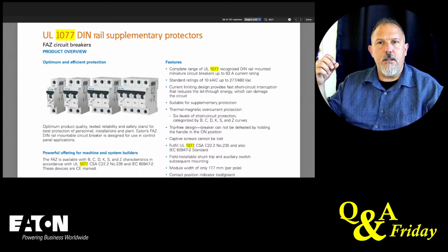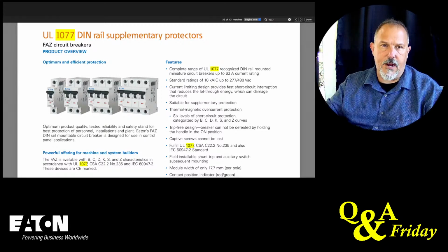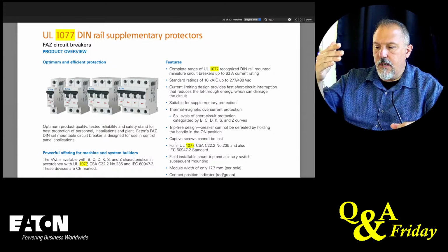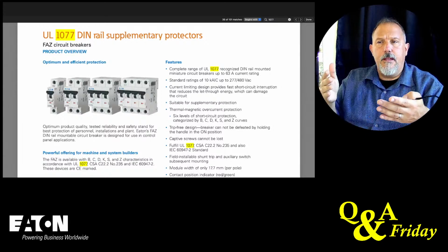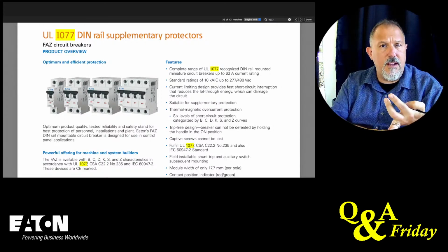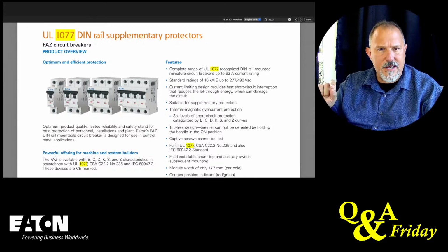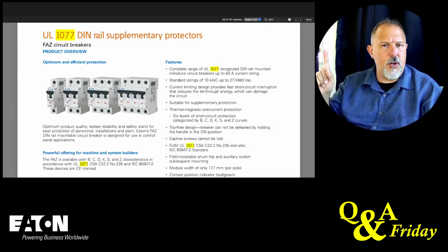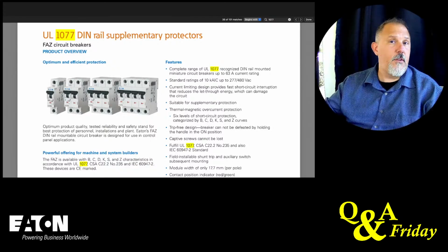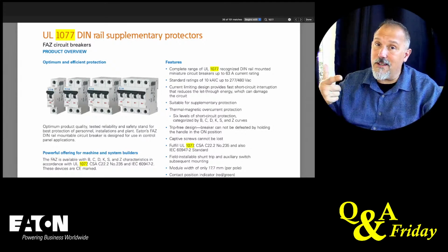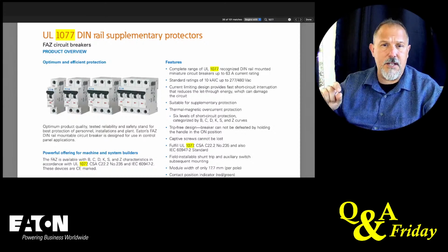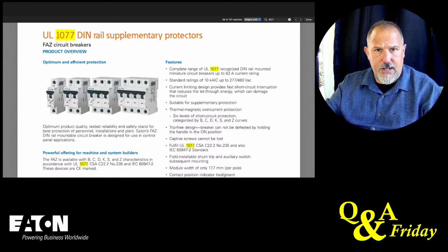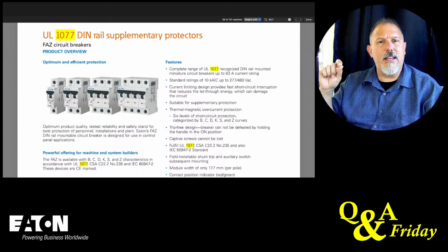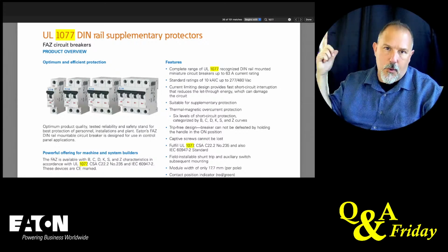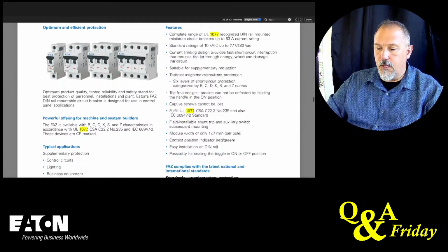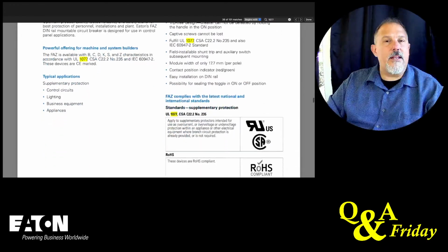These are meant for control type environments where a 1077 type of device is there to provide local isolation and some level of protection, right? But all of these 1077 devices are going to require an upstream branch circuit overcurrent protective device, either to provide protection for the branch circuit coming down to that piece of equipment, or possibly to give you a short circuit current rating or an interrupting rating that you need for that device. That device is not necessarily capable of those very high fault currents, and it needs a big brother upstream. So in any case, let's take a look at what the technical guide tells us.